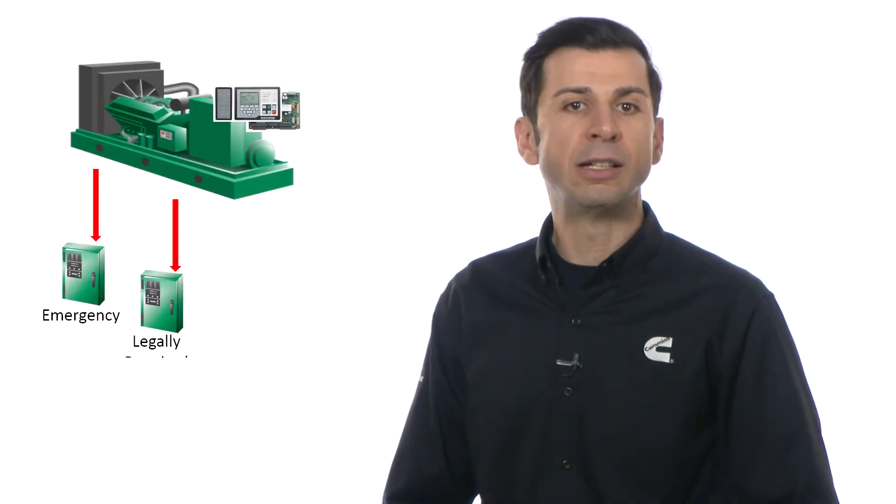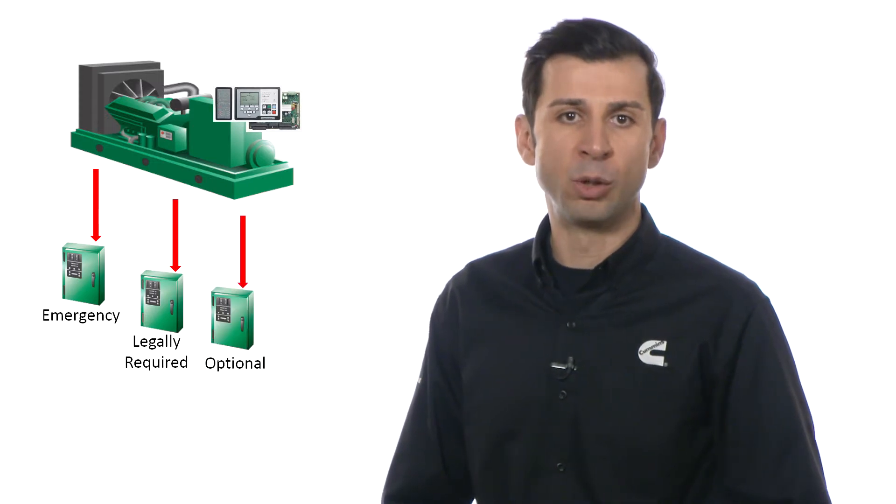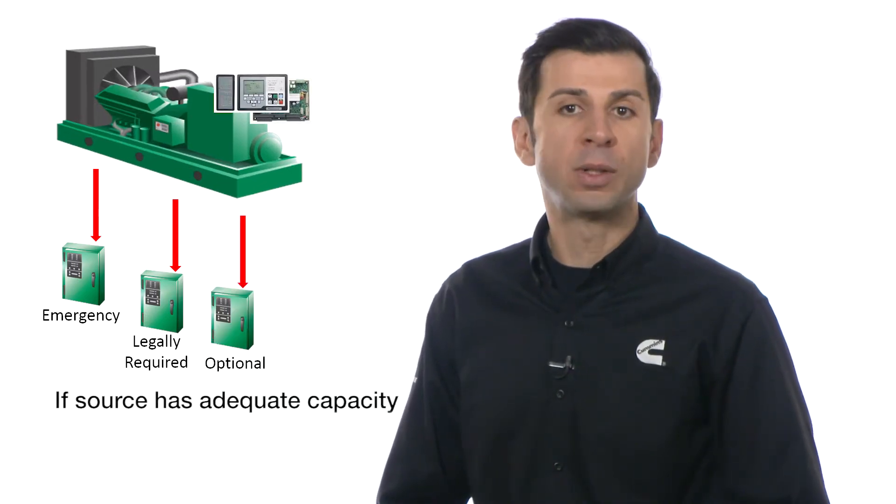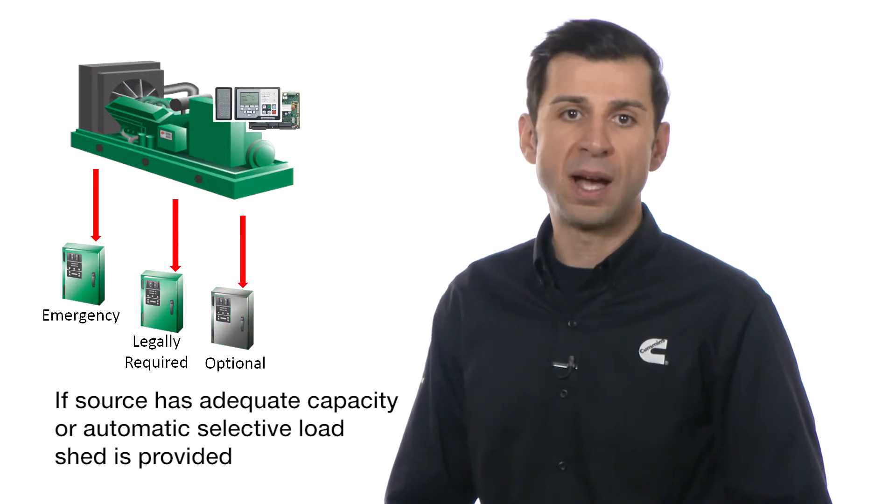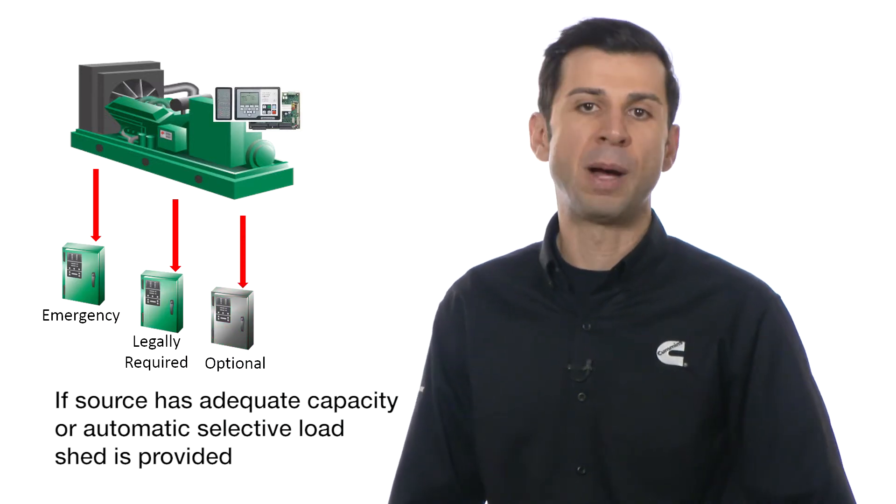The U.S. National Electric Code allows the alternate power source to supply emergency, legally required, and optional system loads where the source has adequate capacity or where automatic selective load shed is provided as needed to ensure adequate power.